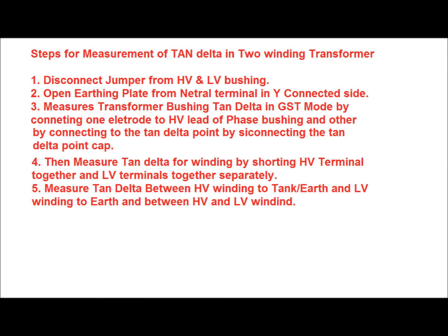Now, what are the steps for measurement of tan delta in a two-winding transformer? First, we have to disconnect the jumper from the HV and LV bushing. Then we have to open the earthing plate from the neutral terminal in the case of the Y-connected side of the transformer. Then we measure the transformer bushing tan delta in GST mode by connecting one electrode to the HV lead of the phase and the other to the tan delta point of the bushing. Before connecting the tan delta point, the tan delta cap should be disconnected from the bushing.